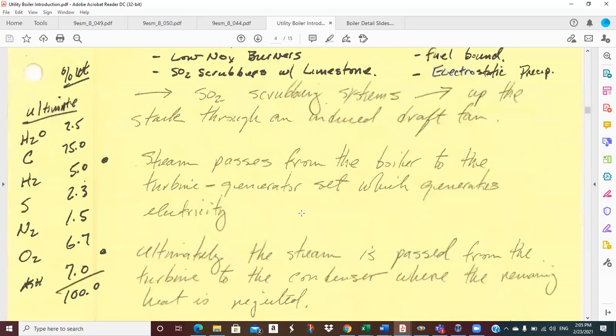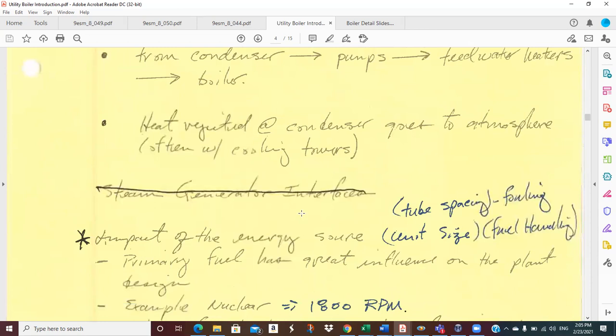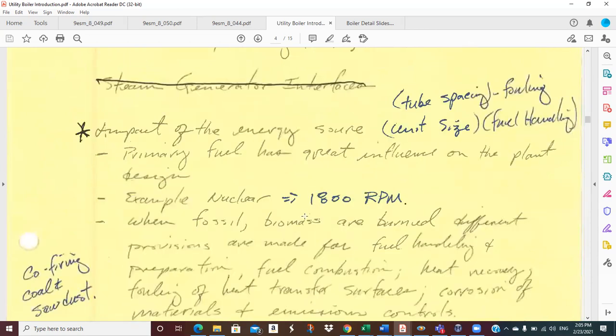Steam passes ultimately. Yeah, this is the stuff we know. Impact of fuel source on the design of the unit. Tube spacing and fouling is an issue. We'll see that for natural gas units, they can be smaller with much closer tube spacing, because there's really no solid matter that can accumulate on the tubes or foul the tubes. Coal units' tubes have to be spread out further, larger tubes and that sort of thing, in order to prevent fouling and to make them more cleanable with soot blowers and things like that. So the fuel has a lot to do with the cost of the unit and the size and that sort of thing.